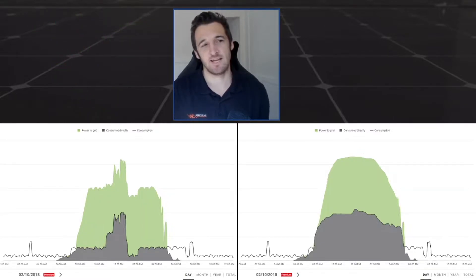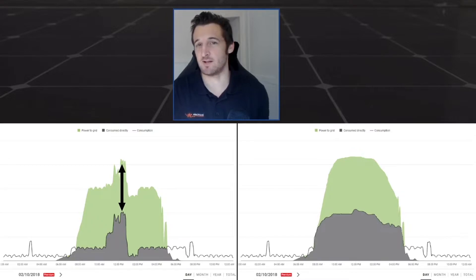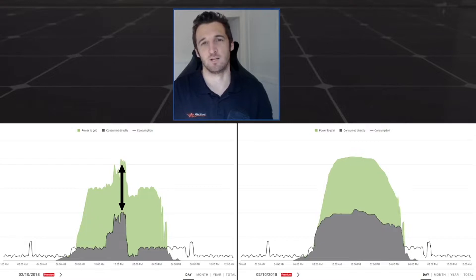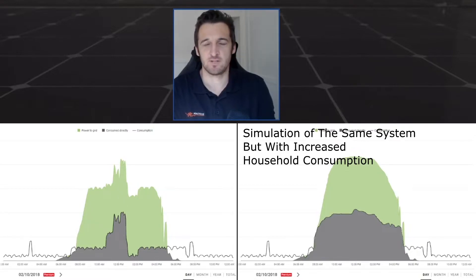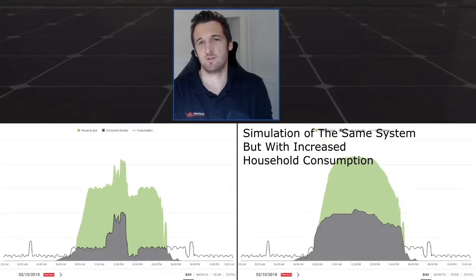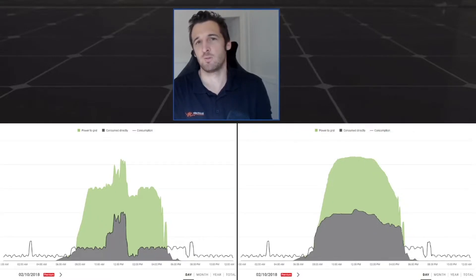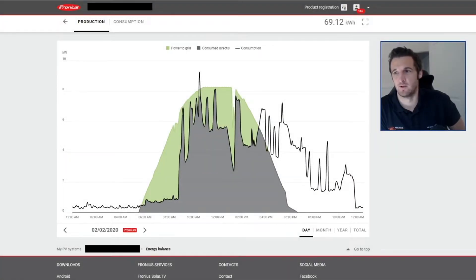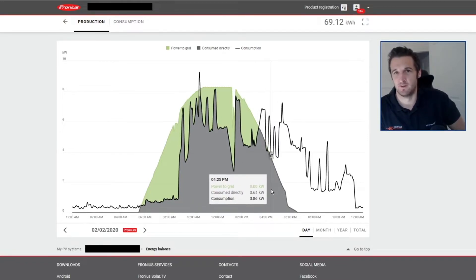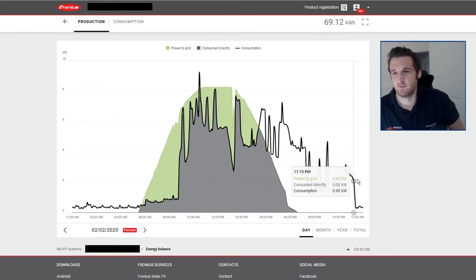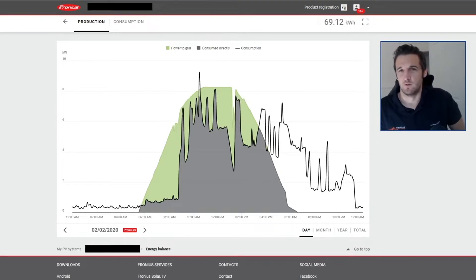In the example to my left you can see how the green section is able to rise in the middle of the day as household consumption rises, because it's able to increase within its five kilowatt export limit. The graph to the right is a simulation showing what the system can get to if household consumption increases throughout the day — it's no longer held back by the five kilowatt export and can reach that 10 kilowatt sizing. This single phase household definitely benefited by installing a larger system. Had they only installed the five kilowatt, their consumption would not have been met, peaking at periods of eight kilowatts — so a system larger than five kilowatts was required.